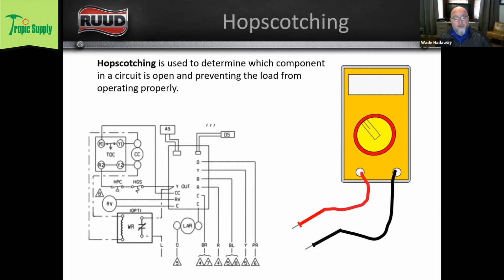So what we're going to do is use a method called hopscotching. And what that means is we're going to start at one end of our circuit and work towards the other end of it to verify where we have power and where we don't have power. So here's our circuit. We're coming out of that Y terminal. We're going through a hot gas sensor. We're going through the high pressure control. Then we're going through our contactor coil, and then we're coming back into CC in our board. So we've got a temperature sensor, a pressure sensor, and then our contactor coil.